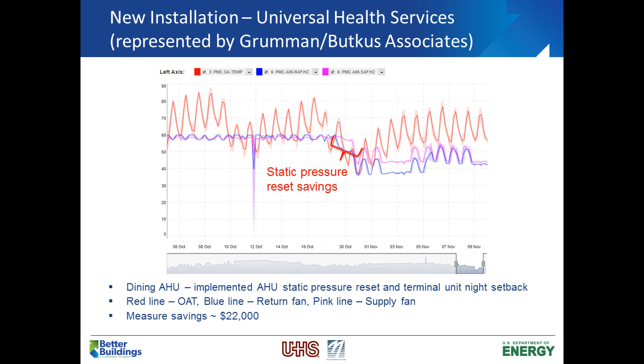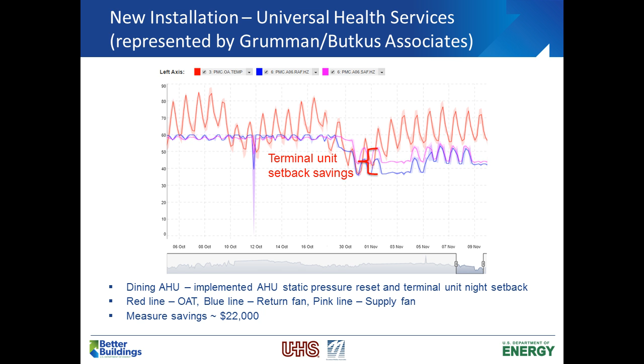Then we also did terminal unit setbacks, so now you see that during the weekends and at night the boxes, the airflow is reduced at the air handler level even more so. So this is really the key to show the before and after picture and how we're able to analyze the data utilizing the platform, and then also to be able to look back and make sure that if all of a sudden the energy of the supply fan started creeping back up, there's obviously been a change to the space or maybe an override has happened. So this is how we monitor to make sure that the measures we implement are continuing on.